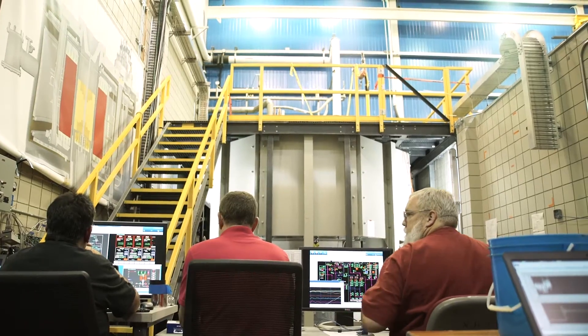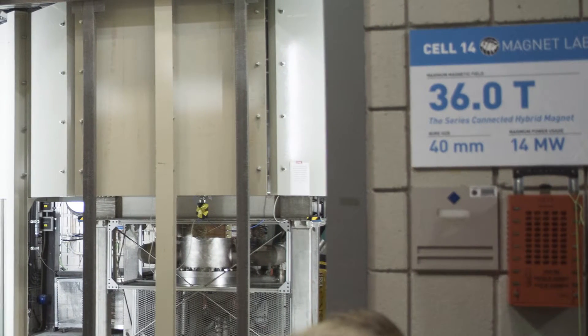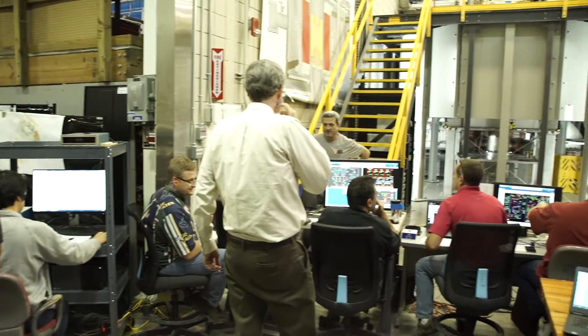Today we've achieved testing of a new magnet system that's going to be put here in the Magnet Lab. It's a 36 Tesla resistive hybrid NMR magnet. This magnet system represents a huge increase of what's available for NMR science today — right now it's over 20 Tesla for NMR magnets, but now it's up to 36 Tesla.